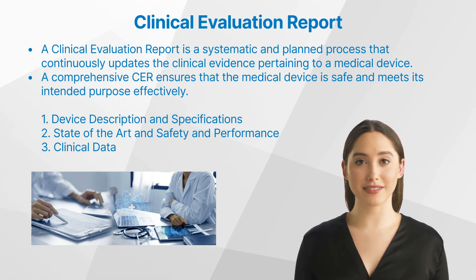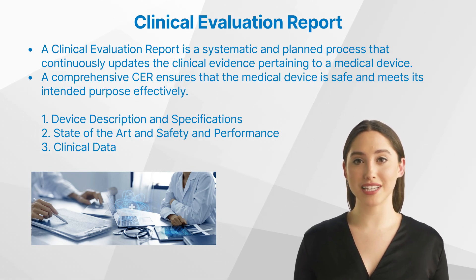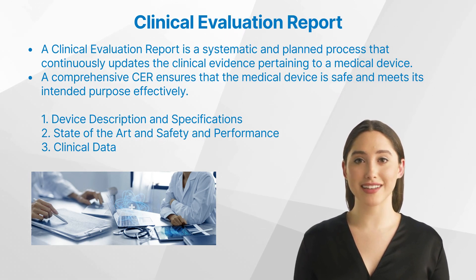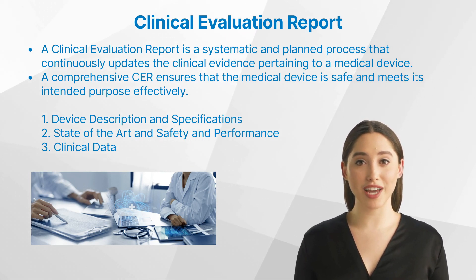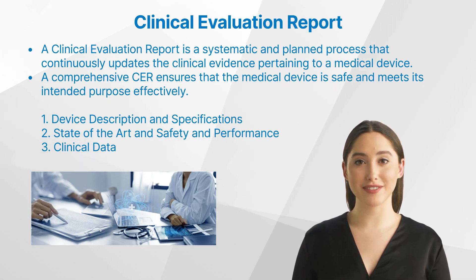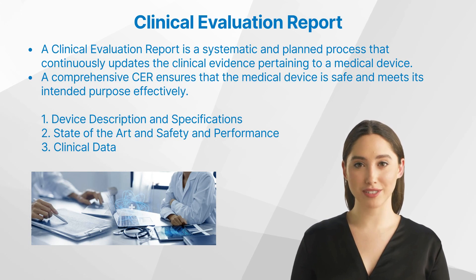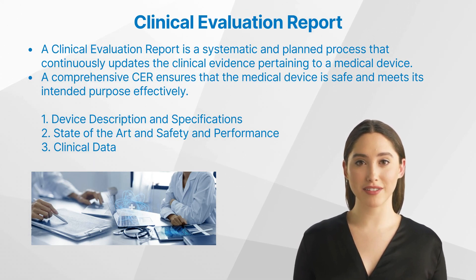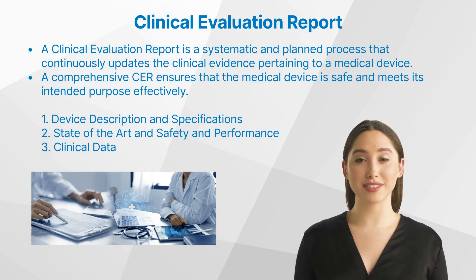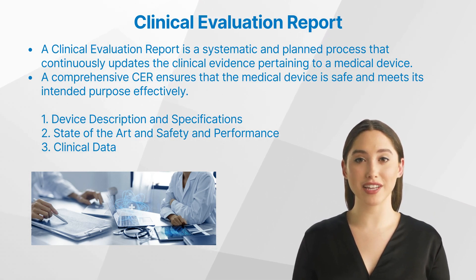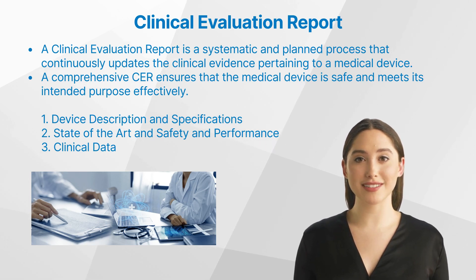Three: clinical data. The third component requires collecting clinical data pertaining to the device. This includes both preclinical — laboratory and animal studies — and clinical human trials data. The data should provide evidence of the device's safety, performance, and potential benefits and risks. It should also be specified if the data is based on the device being evaluated or for a comparable device. If it is for a comparable device, a justification of equivalence needs to be provided.